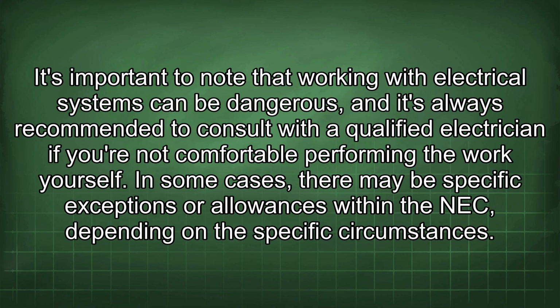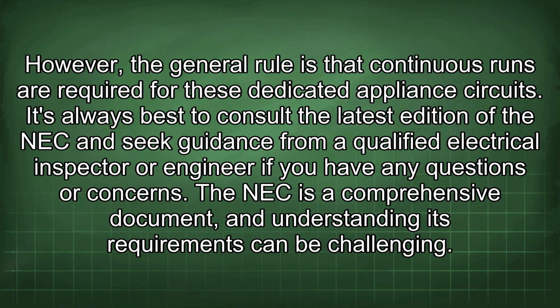It's important to note that working with electrical systems can be dangerous, and it's always recommended to consult with a qualified electrician if you're not comfortable performing the work yourself. In some cases, there may be specific exceptions or allowances within the NEC depending on the specific circumstances. However, the general rule is that continuous runs are required for these dedicated appliance circuits. It's always best to consult the latest edition of the NEC and seek guidance from a qualified electrical inspector or engineer if you have any questions or concerns.